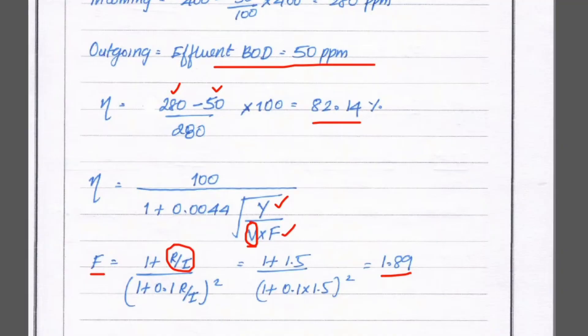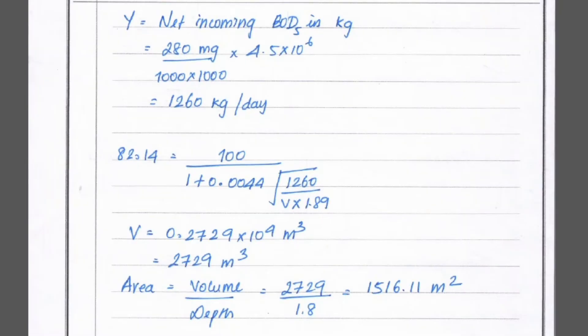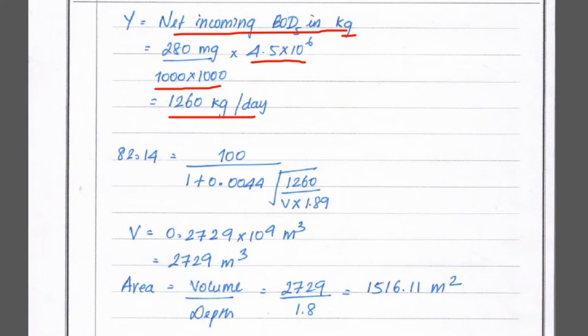Next, we find the y value, which is the net incoming BOD in kg/day. Incoming BOD is 280 ppm. Converting: y = 280 / (1000 × 1000) × 4.5 × 10⁶ = 280 × 4.5 = 1260 kg/day. So y = 1260 kg/day.